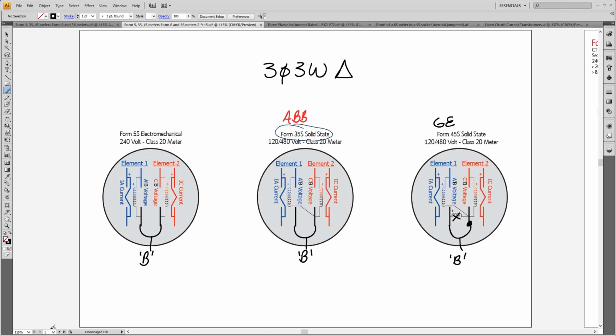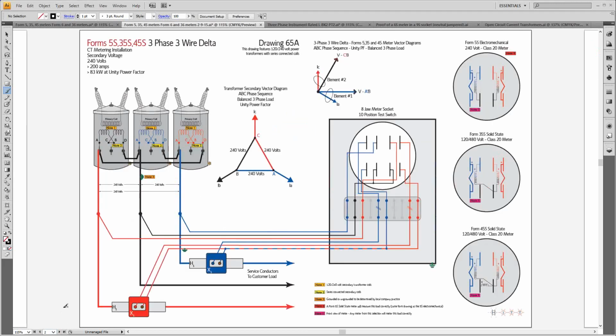Having all that said, I'm going to a diagram for three-phase, three-wire delta. It's one of the things we talked about last week, how the vector diagram would be set up for the meter itself. This is for what would be seen as ABC phase sequence. The first potential coil in my meter, in all three meters, has A to B voltage across it. So in the 5S, A to B voltage is across this potential coil.